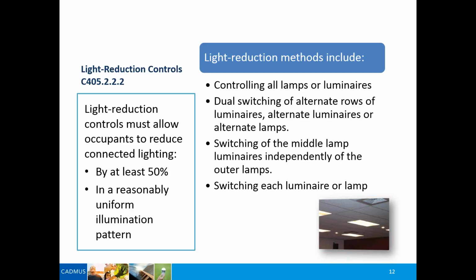And there is no exact science for how this is done. From a design standpoint, it's always a challenge to figure out how to do this. From a jurisdictional standpoint, it's always a challenge to review the plans to make sure that they've done it correctly. But again, this requirement hasn't changed. Now, the only exemption on this is if you have a space with a daylit zone in there. I'll talk about daylight zones in the next slide. Then you are not required to have bi-level switching, because the daylighting controls will automatically do this for you. It'll automatically dim the lights if you have sufficient light coming in from the outside to be able to light the space on the inside.